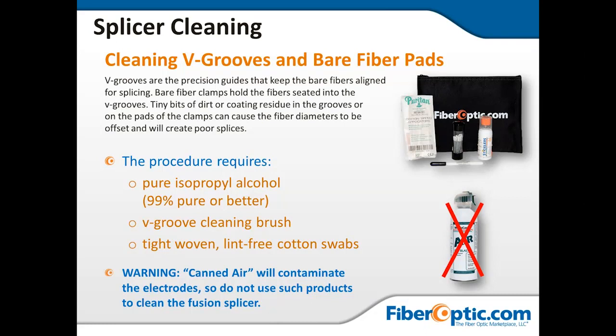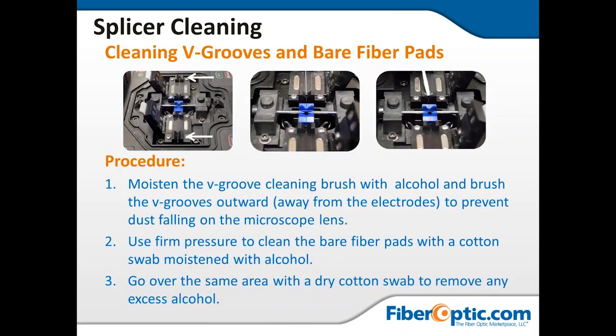The procedure requires pure isopropyl alcohol, 99% pure or better, V-groove cleaning brush, tight woven lint-free cotton swabs. Must emphasize this: do not at any time use canned air on cleaning your electrodes. That will contaminate them. Cleaning V-grooves and bare fiber pads. Procedure: 1. Moisten the V-groove cleaning brush with alcohol and brush the V-grooves outward, away from the electrodes, to prevent dust falling on the microscope lenses. Use firm pressure to clean the bare fiber pads with a cotton moist alcohol swab. Go over the same area with a dry cotton swab to remove any excess alcohol.